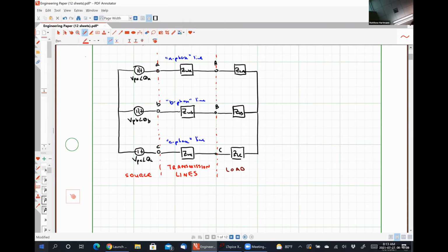So in this system, which is called a three-phase, three-wire system, or you may see it as 3Phi 3W on technical documents, we can actually transmit 3 times as much power as the single phase system that I've drawn above, using only 1.5 times the number of wires.